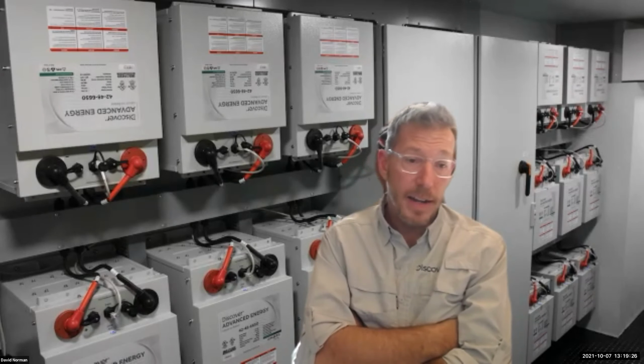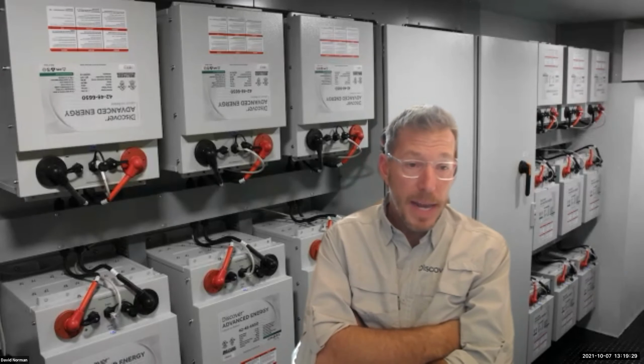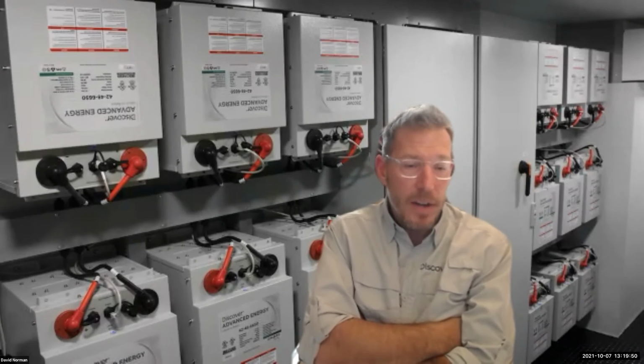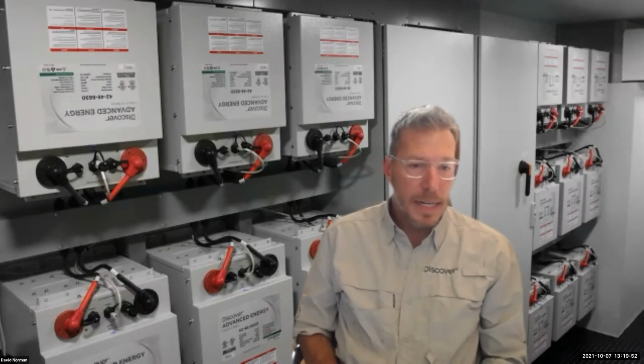Or if you have a charging source the whole winter and you have some means of external heat, whether that's thermal, solar thermal, or some kind of a load bank in a well-insulated room, or if you're running loads regularly. You have to keep in mind the inverter charger is about 93% efficient, so 7% goes to heat. The batteries are 95 plus, so there's another 5% there that can create enough heat in a well-insulated room to keep it thermally fine anyway. It all matters to the extent that you're going to.